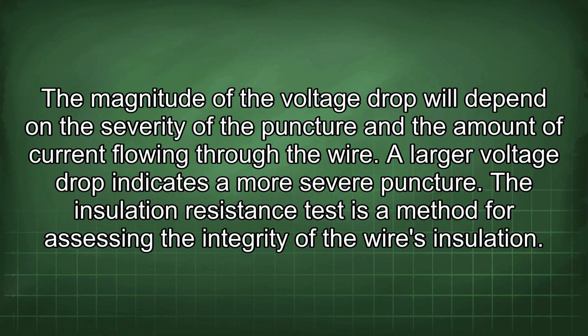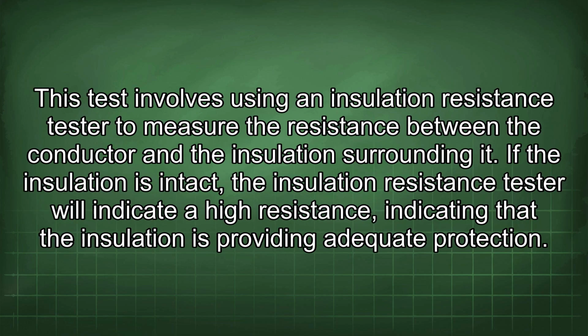The magnitude of the voltage drop will depend on the severity of the puncture and the amount of current flowing through the wire. A larger voltage drop indicates a more severe puncture. The insulation resistance test is a method for assessing the integrity of the wire's insulation. This test involves using an insulation resistance tester to measure the resistance between the conductor and the insulation surrounding it.